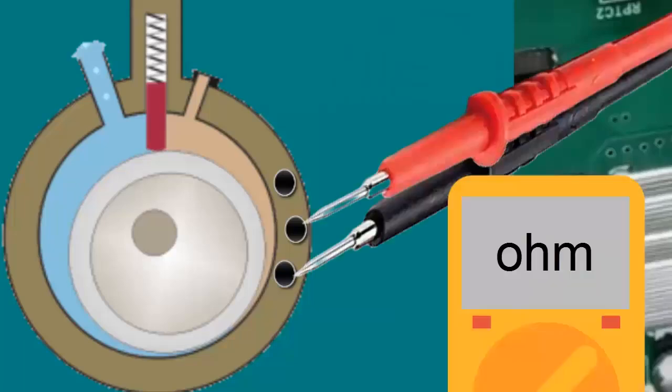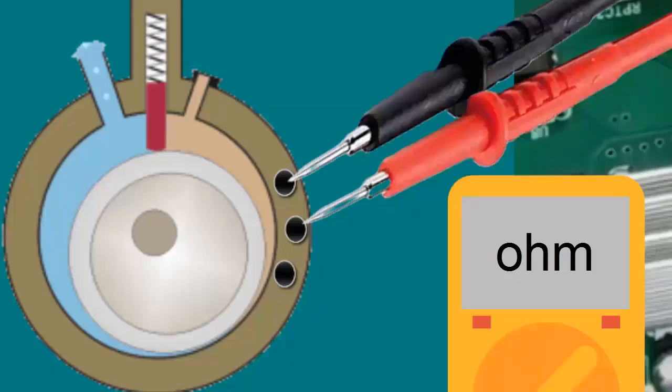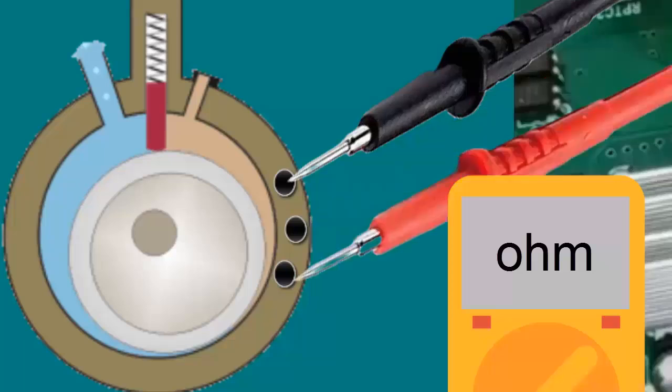D. Verify that the electrical resistance measured between the compressor pins has the correct value. For example, in inverter units, ensure all resistances between pairs of pins have the same value.